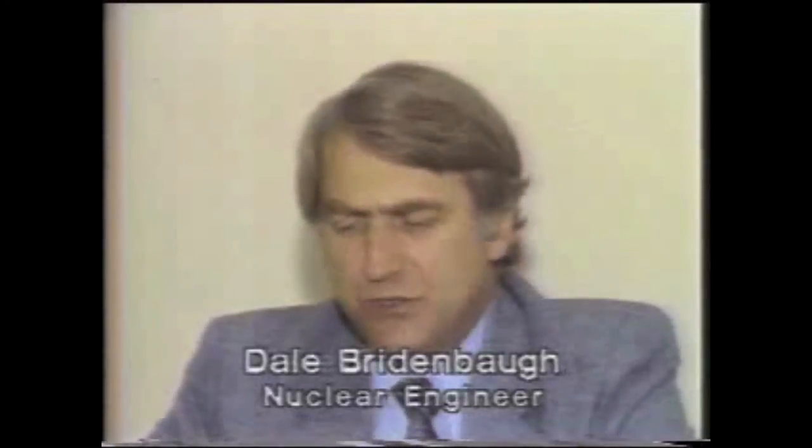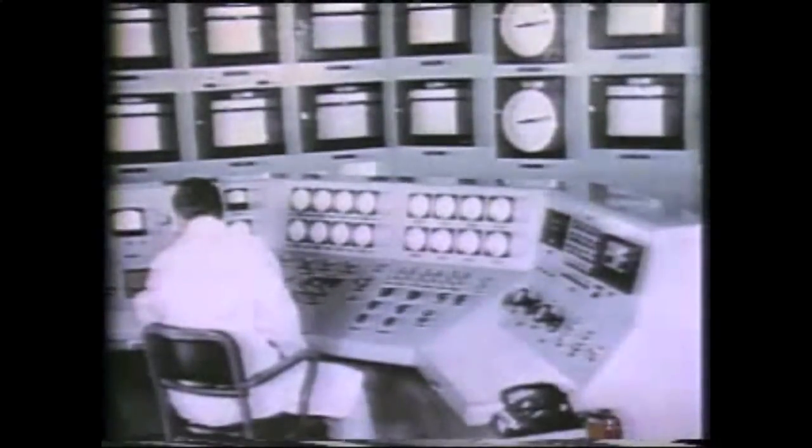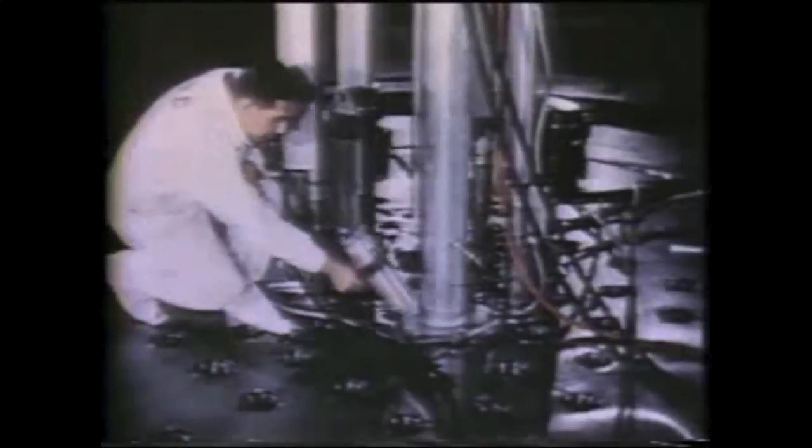What were the potentialities there? There were a lot of things they didn't know about what had caused the power excursion. They were measuring high radiation release levels within the reactor building and didn't know why. They didn't know what the reactor core condition was, but for some reason they felt they needed to get back in operation. The reactor continued to run for another two weeks, even though there was more trouble. It was shut down repeatedly, including for buildups of radioactivity in the building above the reactor. That led to the final shutdown, 13 days after the first signs of trouble.